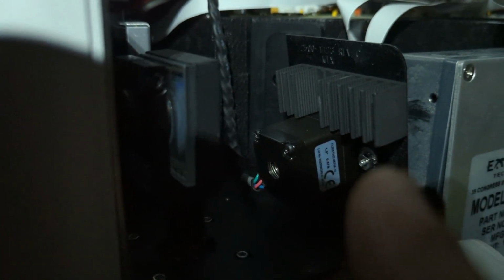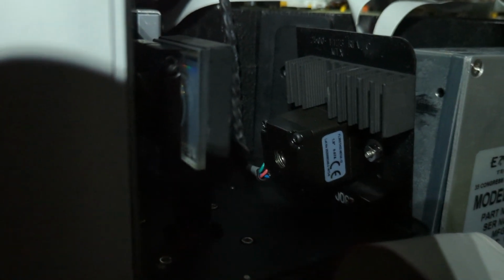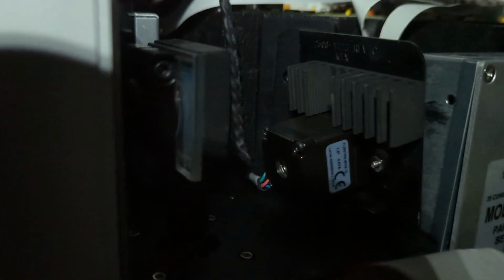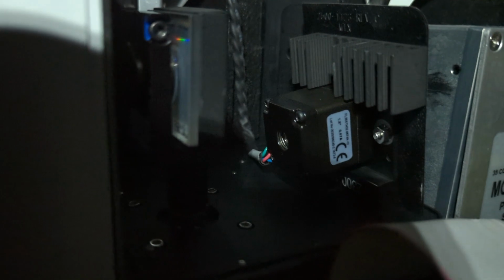I can show you guys in a second a few of the runs that I did that'll show this, but when I moved it all the way forward, using that adjustment screw at the top there, then all the wavelengths got smushed, so the resolution got really poor, and it made them a much lower value than they should be. So that is really important, the adjustment forward and back. Now, one thing I will point out is when it's going through the initial cycling of the filter wheel, if you don't have it positioned properly, it'll stop immediately and give you this filter wheel error, and that's what it was doing initially.